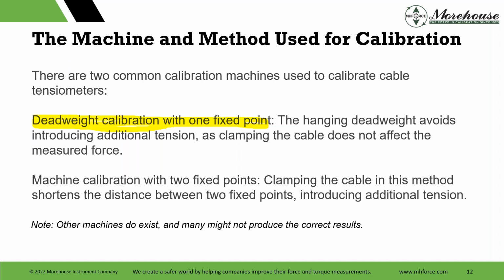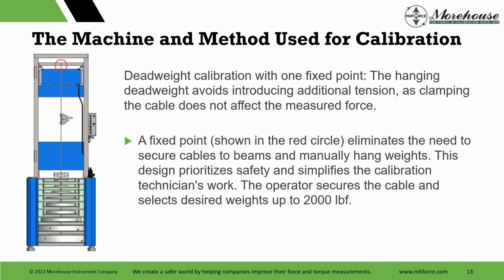And then machine calibration with 2 fixed points. So you have 2 fixed points, you clamp the cable, guess what? You shorten the distance, create more force. So clamping the cable shortens the distance between these and then introduces additional tension. And other machines exist that lie vertical, some lie horizontal. They wouldn't really lie, they stand vertical or they lie horizontal. So those machines might work. There's different ones that have been discontinued over the years, probably because they don't work. There's other methods to back calculate torque. Lots of errors to try to back calculate torque to convert a force and know the length. That's something else that I don't think is very good.